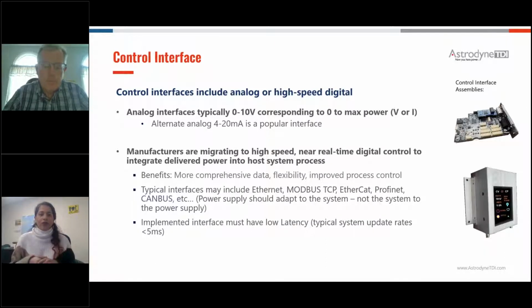All right, so with your power supply, there are also different kinds of control interfaces that you can take into account. In laser applications, I think it's typically analog or high-speed digital. Gary, can you tell us from your experience what you've seen and the benefits of either way? So certainly the typical application has an analog interface where, more often than not, it's a 0 to 10 volt signal that corresponds to 0 to maximum of the delivered parameter, whether it's voltage, current, or power. Many times in industrial settings, you do see a 4 to 20 milliamp interface that provides a little bit more noise immunity. So that's typically what you see.